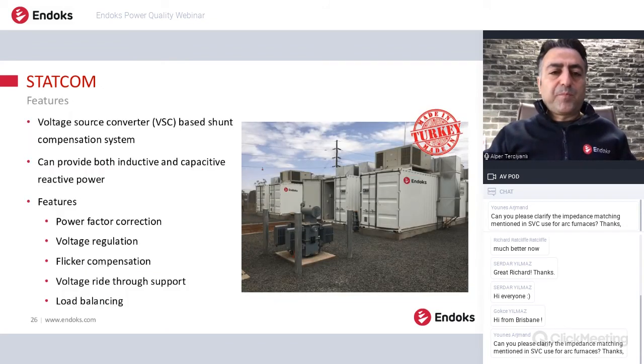And like SVC, STATCOM also can create reactive power, but since it is a controlled device, unlike the SVC or unlike passive systems, we can generate either inductive or capacitive reactive power from the same converter. It is the main advantage of this STATCOM. And also the response time is very, very fast, because in STATCOMs we are using IGBTs as semiconductor devices, and the response time of the IGBTs is around milliseconds. So the response time is very fast compared to SVC.